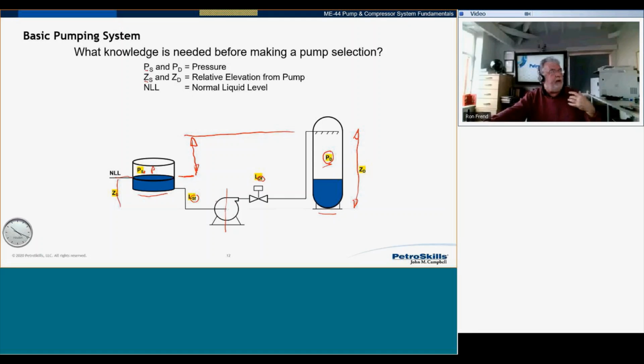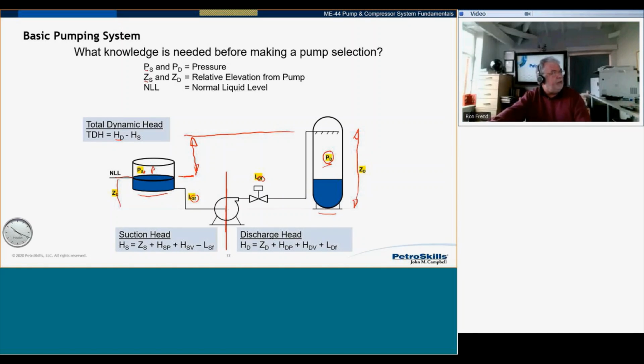As soon as the pump starts to operate and liquid starts to flow through that system, then we are going to get some losses. And again, I've got to add energy into the liquid to overcome those losses. So we said the total dynamic head is the head on the discharge minus the head on the suction. And the suction head is elevation plus the pressure. There's something we haven't really mentioned, which is velocity head. I add all those three together, and then I subtract the friction losses. What this is telling me is how much energy my liquid has right here at the suction to the pump. On the discharge side, I've got exactly the same elevation, pressure, velocity head, and friction.